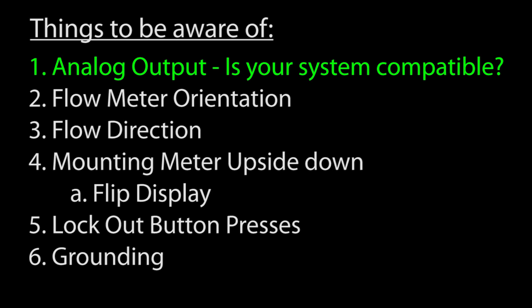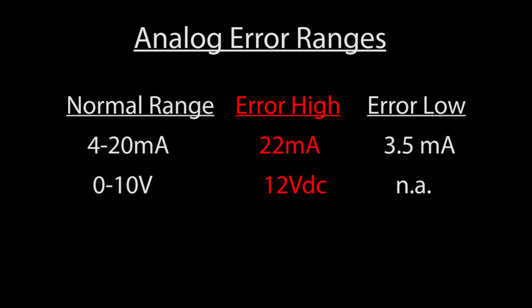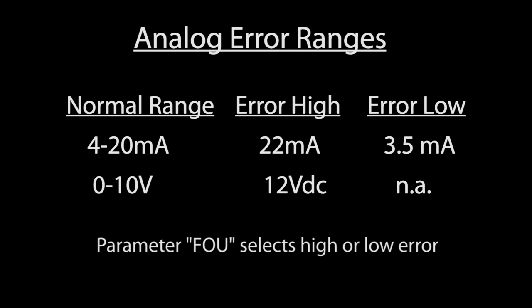First, you can specify what you want the analog output to do in case of an error. It can go to a high value or a low value or just output the measured value. Please make sure your equipment can handle currents and voltages outside the 4 to 20 milliamp or 0 to 10 volt range before using these options.